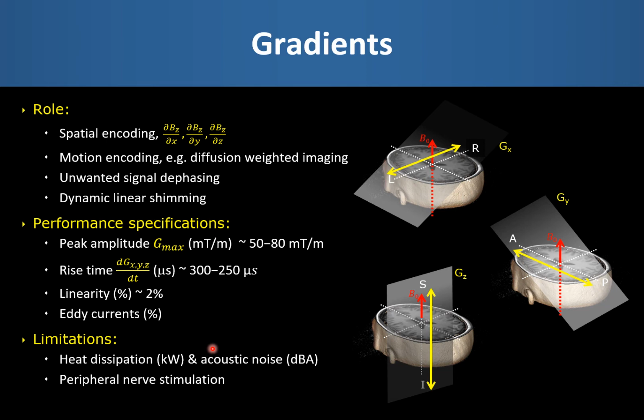In terms of the limitations, gradient switching can generate quite high levels of acoustic noise. So there is a requirement to ensure that patients and anybody else who happens to be in the MR environment during the scan has appropriate hearing protections. In order to generate the high performance gradients, we require substantial currents and voltages to be generated in the amplifiers and then passed through the gradient coils. So both the amplifiers and the gradient coils themselves need to have a chilled water supply in order to dissipate the heat that is generated. Finally, gradient switching can cause peripheral nerve stimulation that can range from a tingling sensation to, albeit very rarely, painful muscle contractions.